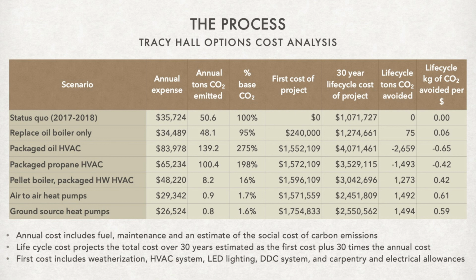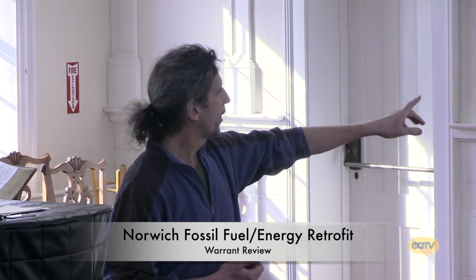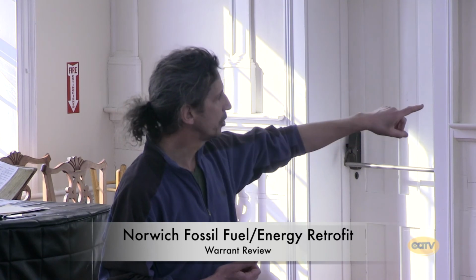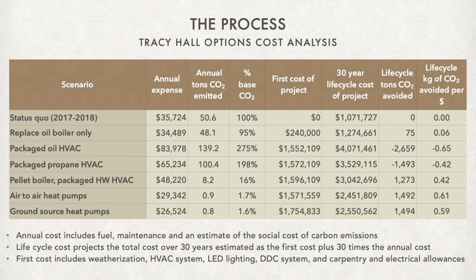30-year life cycle cost just means the first cost plus 30 times the annual cost. Pretty simple - I didn't worry about interest on the bond. Yes, there's interest on the bond, but that's true for all of them, we'd have to borrow the money for all of them, so I just left that off. By this life cycle cost, air-to-air heat pumps come out cheapest in this table because they're significantly cheaper, $200,000 cheaper to build. The annual difference between ground source and air-to-air heat pumps in efficiency is only a couple thousand dollars a year, so over 30 years that's not enough to overcome the difference in first cost.